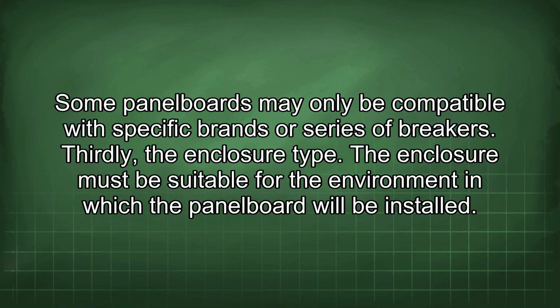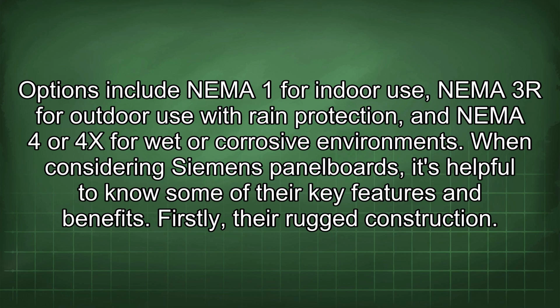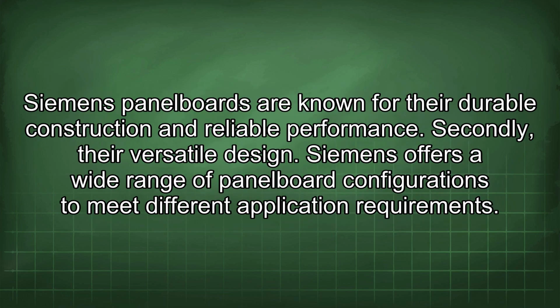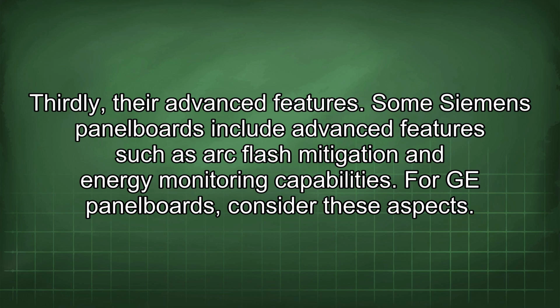Thirdly, the enclosure type. The enclosure must be suitable for the environment in which the panel board will be installed. Options include NEMA 1 for indoor use, NEMA 3R for outdoor use with rain protection, and NEMA 4 or 4X for wet or corrosive environments. When considering Siemens panel boards, it's helpful to know some of their key features and benefits. Firstly, their rugged construction. Siemens panel boards are known for their durable construction and reliable performance. Secondly, their versatile design. Siemens offers a wide range of panel board configurations to meet different application requirements. Thirdly, their advanced features. Some Siemens panel boards include advanced features such as arc flash mitigation and energy monitoring capabilities.